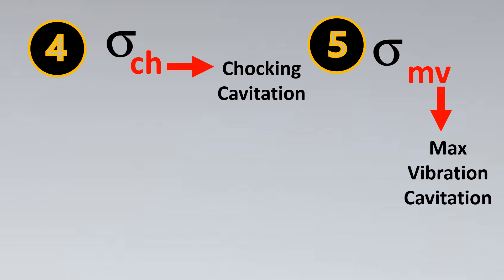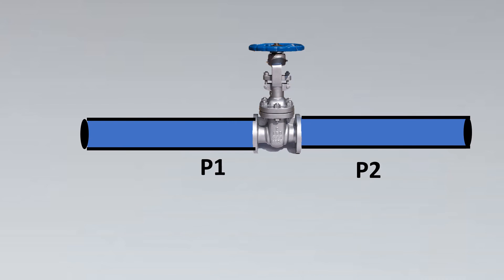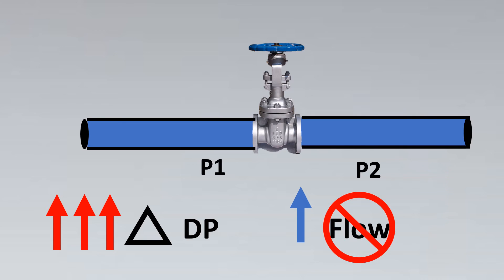Now we have the fourth criteria, which is sigma CH with the suffix CH, which is choking cavitation, and the final one, which is maximum vibration cavitation. These both are very similar to each other and very simple but very essential. Imagine this is your valve and this is your pressure drop happening. We are very sure with the concept that if we increase dp, there is going to be an increase in flow, but if we keep increasing dp, at a point of time flow will not increase. This point is called choked flow.